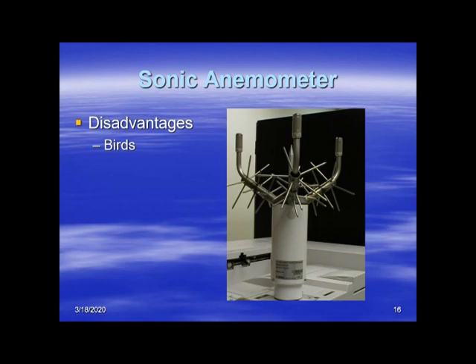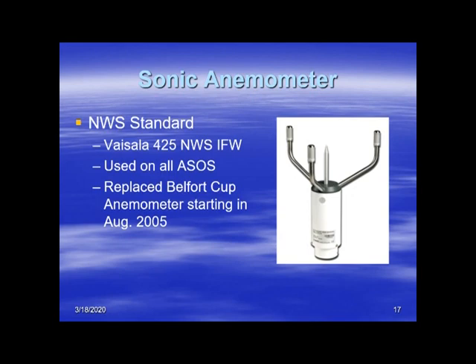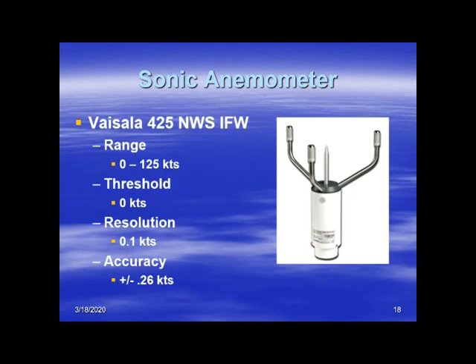The National Weather Service transitioned over in 2005 to sonic anemometers. They use a Vaisala 425 National Weather Service ice-free wind sensor, which is standard on all ASOS stations across the United States. The Vaisala 425 has a range of 0 to 125 knots, a threshold wind speed of 0, resolution down to one-tenth of a knot, and an accuracy of about a quarter of a knot.